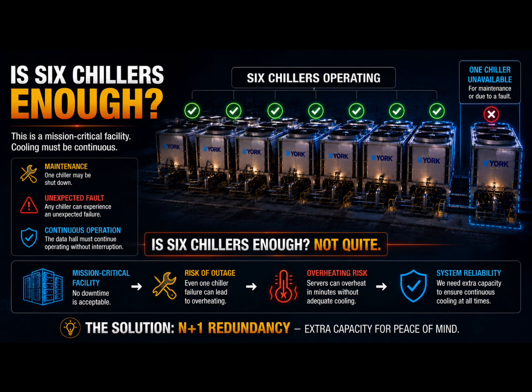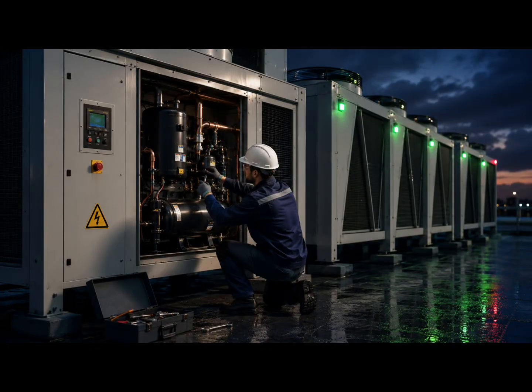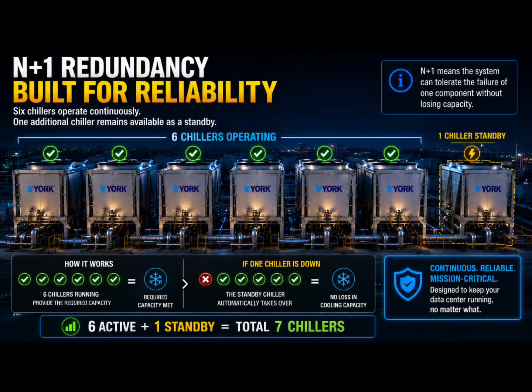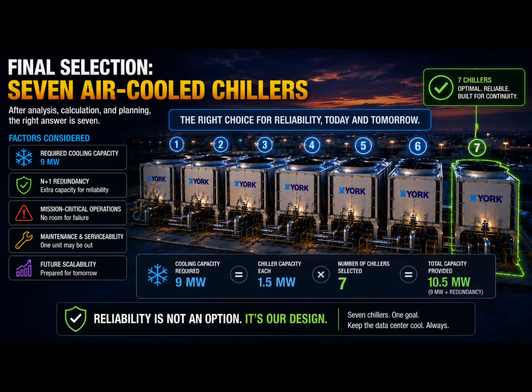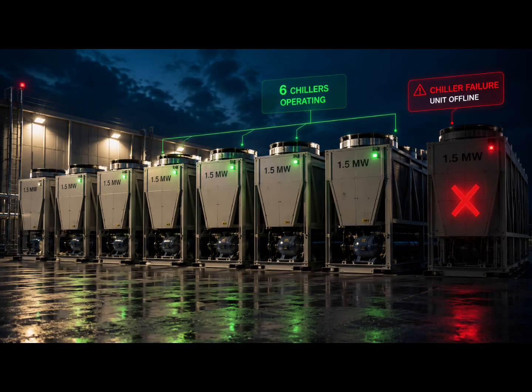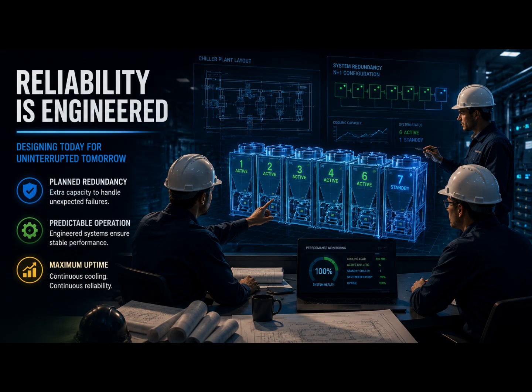Not quite, because once again, this is a mission-critical facility. If one chiller is shut down for maintenance or experiences an unexpected fault, the data hall must continue operating without interruption. So once again, we apply N+1 redundancy. 6 chillers operate continuously. 1 additional chiller remains available as a standby. Our final selection becomes 7 air-cooled chillers. This ensures the required cooling capacity remains available even if 1 chiller is unavailable. Reliability is never an accident.